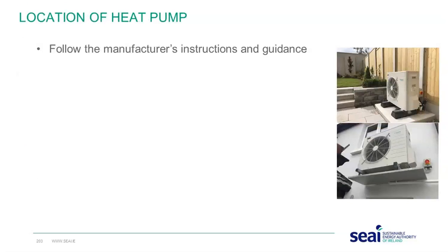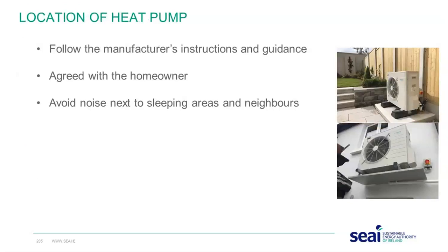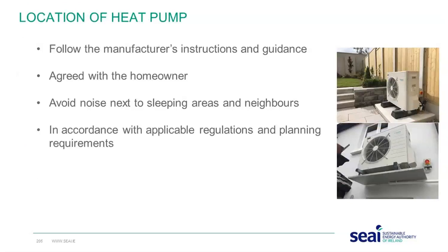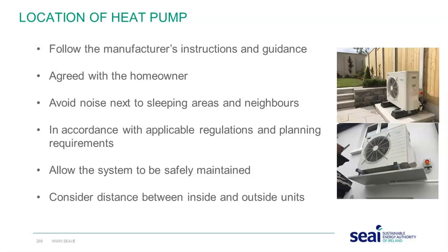So, locating the heat pump, we ask you to follow the manufacturer's instructions and guidance, and agree it with the homeowner. Take the time and discuss it with them, ask if they have a preference, and obviously, if there's going to be noise, will there be any nuisance? Was there a better position? You appreciate heat pumps aren't particularly noisy, but in a very quiet setting it may be audible. It must be in accordance with applicable regulations and planning requirements, and please consider accessibility and maintenance in the future. Consider the distance between the indoor and outdoor units, because the volume of refrigerant is defined by the distance between them.